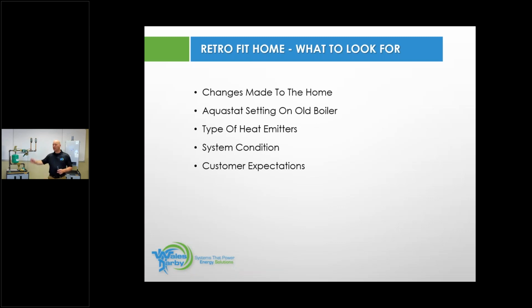Okay, when the person put the baseboard in, they only drilled the 7/8 or whatever, a 1-inch hole, and you got 7/8 pipe going through there that's expanding on outside diameter 7/8, and it expands and it creaks. I don't know that we're fixing that problem in the basement, right? If they don't have enough heat emitters in a room, we probably are not fixing that just by changing out the boiler or working in the basement. So have that conversation with the homeowner, know what their expectations are, know what their current potential problems are, and see if you can address them with changing out the boiler.